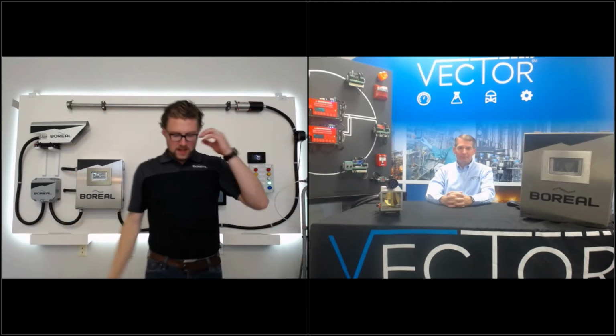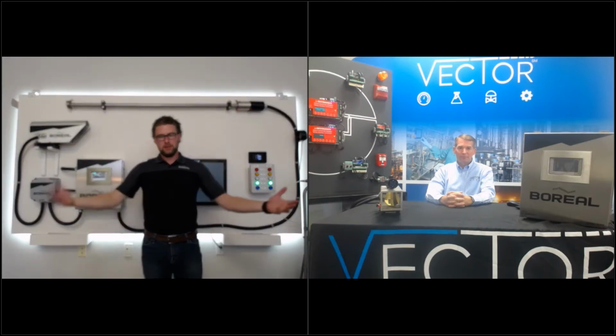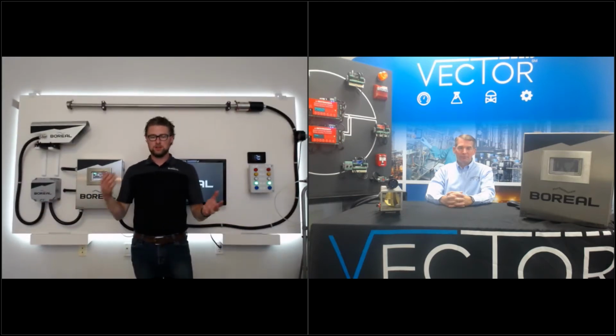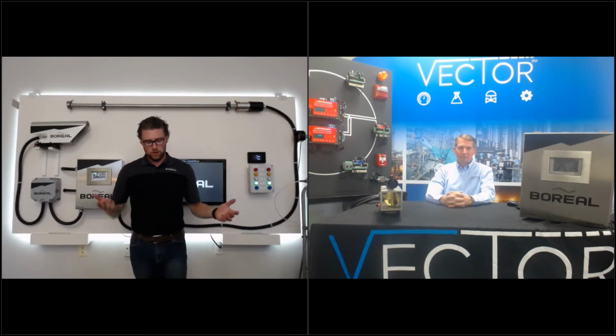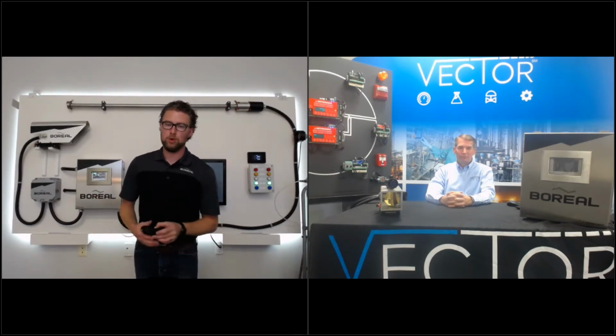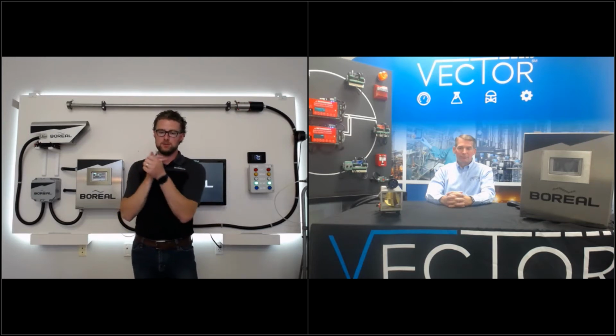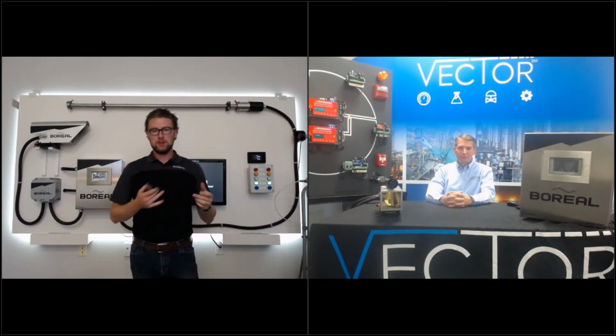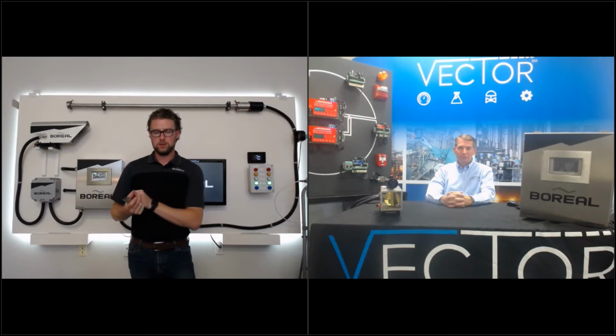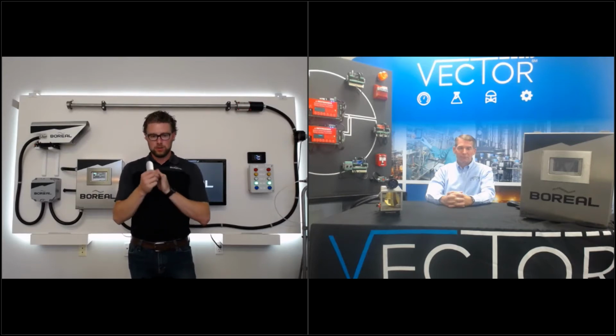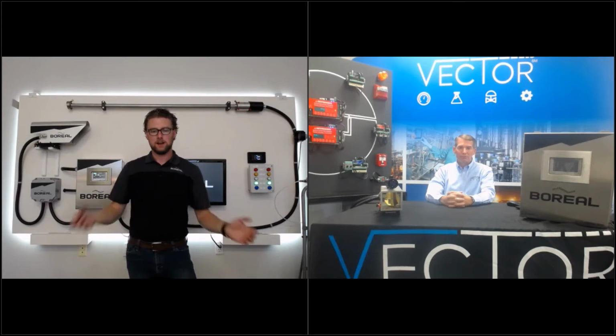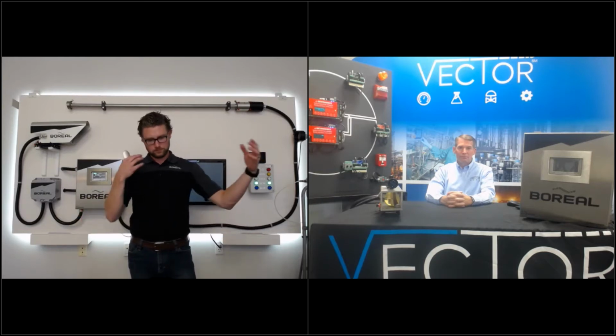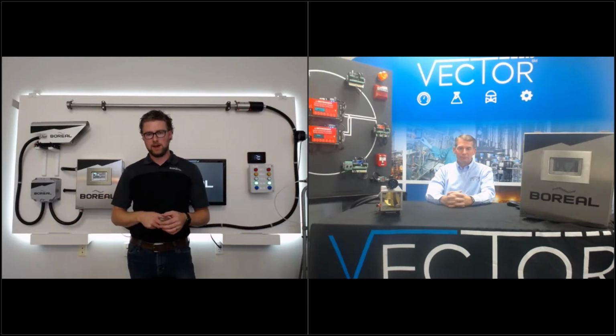So how this system works is we emit laser light at a specific frequency that is tuned to see that particular gas of interest. So why is that important? This is important because we see one gas and we see one gas only. So this makes us perfect for quantitative measurements. We can tell you exactly which gas we see, and we can tell you exactly how much of that gas is present in that active measurement path.